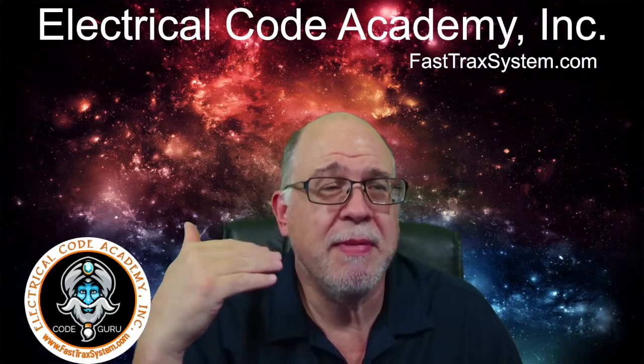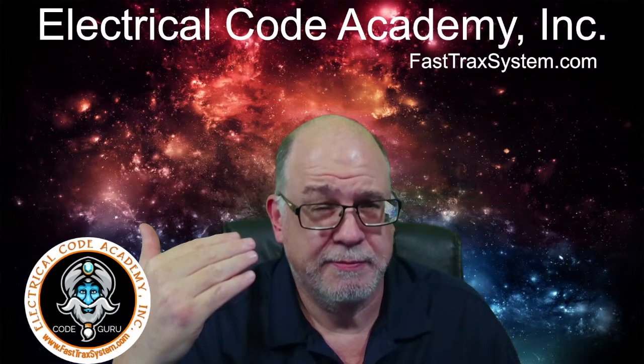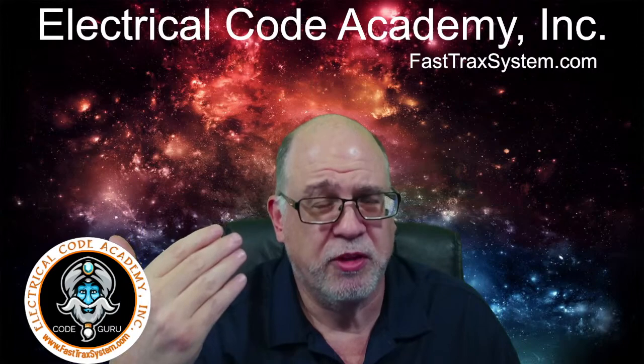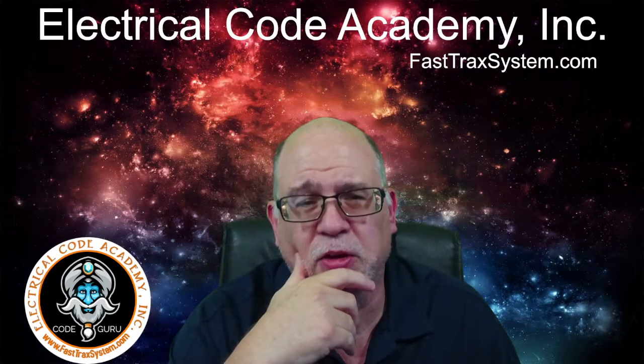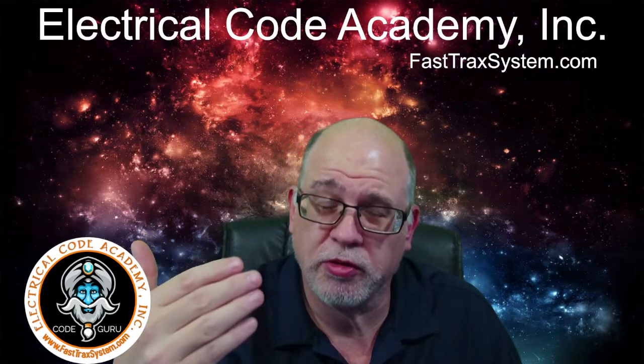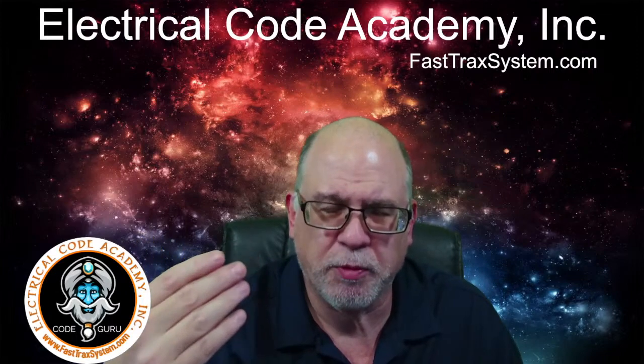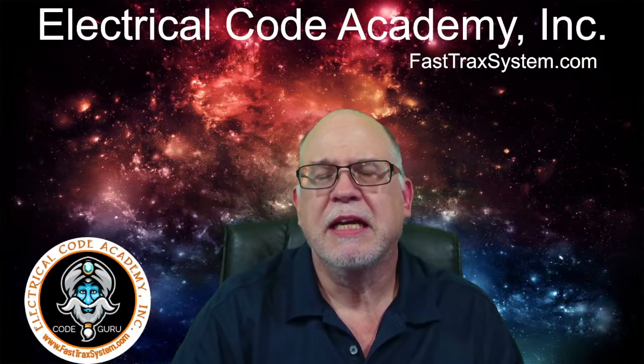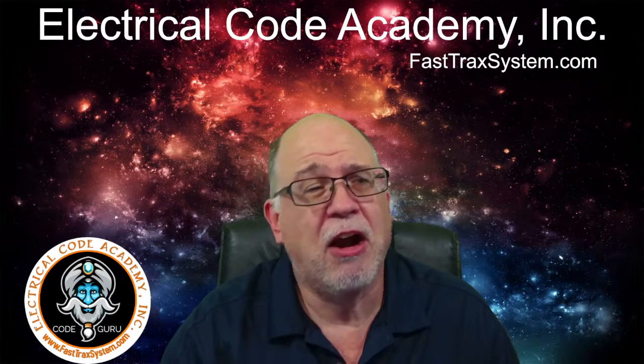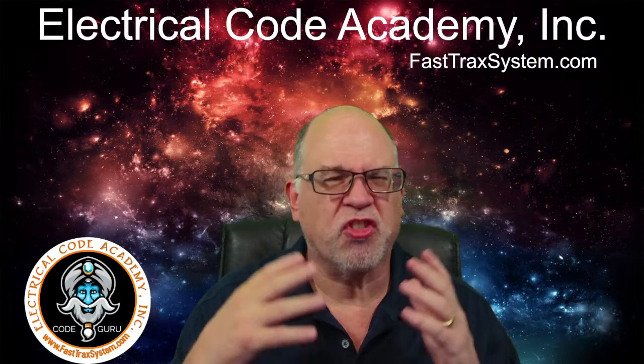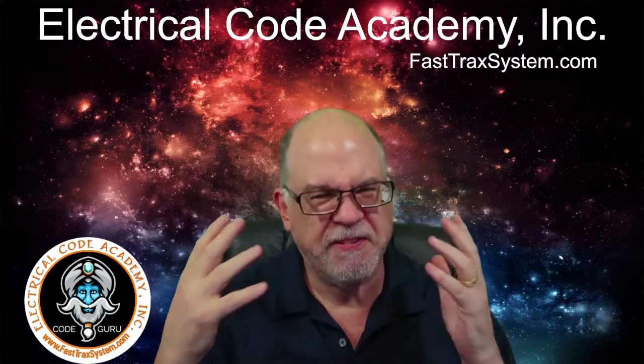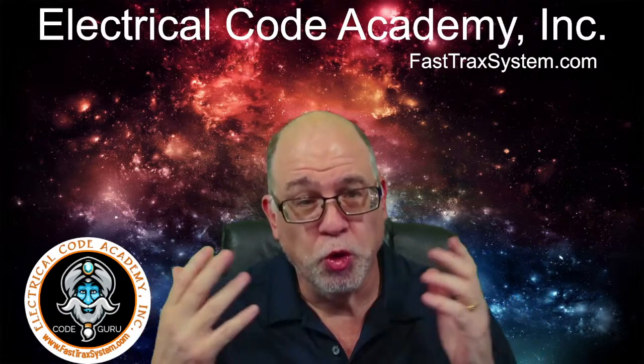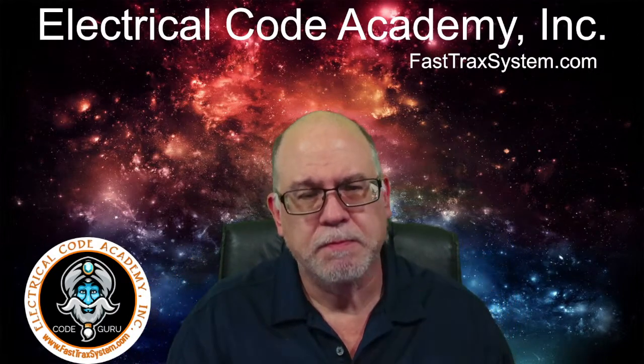But what about the amount that's over 200? He's talking 200 amps. So the code typically allows for that value that's over 200 to be taken at 70%. Let me give you an example. So if I had a calculation for a neutral, for a service, and it was 250 amps of neutral load. We calculated it out.